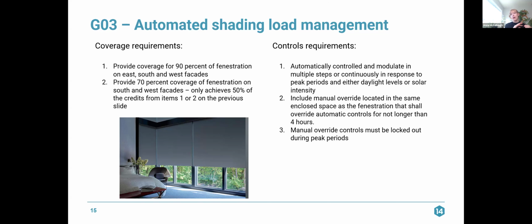You have to include a manual override located in the same enclosed space as the fenestration that shall override automatic controls for not longer than 4 hours. So say you have a conference room, it's not a peak period, but someone wants to close all the shades because they're doing a presentation. They can override those automatic controls that would either allow daylight or not allow daylight for no longer than 4 hours. And then it will reset and the person would have to override it again if necessary. But manual override controls must be locked out during peak periods. So that means if you are having a peak demand event that is being controlled by an entity, those manual controls will not work during that peak period, if someone wants to, for example, open the shades during a peak period.